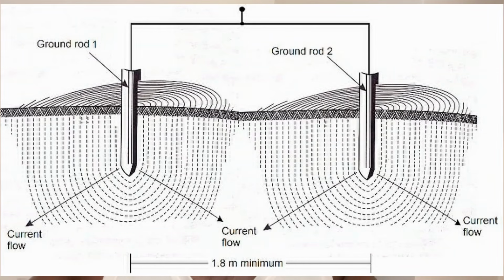Now, if you're too late for the foundational earth system, then obviously you've got no choice but to use the earth rods. Earth rods can work, but they're not as efficient and don't give you a very low earth resistance. The earth rod themselves can corrode, especially in Ghana if you don't get the right earth rod material. Sometimes if you don't buy it from the right place, you can get a copper coated earth rod, and it's not the right pure copper. Yeah, if you know what I mean. That means it will lose its effectiveness over time.